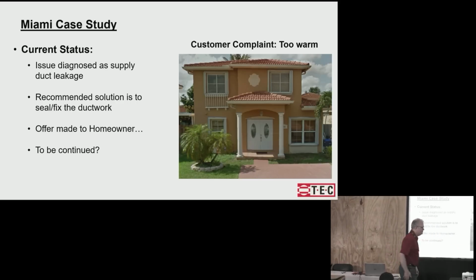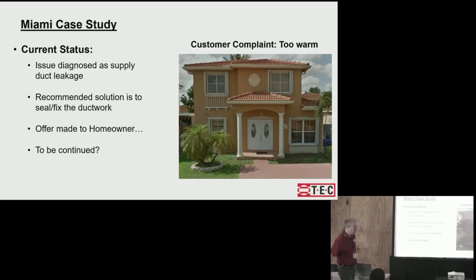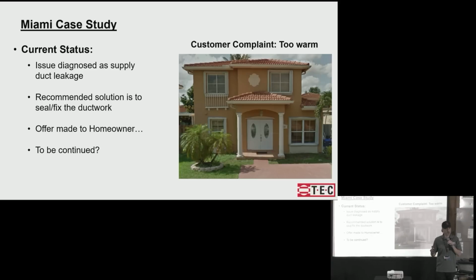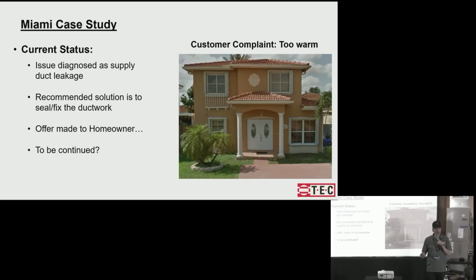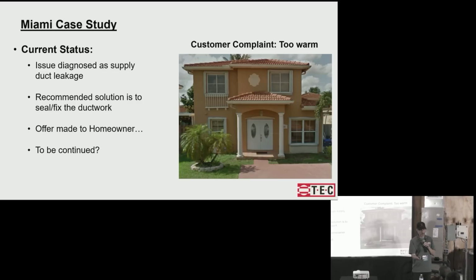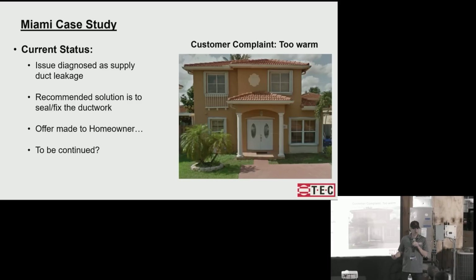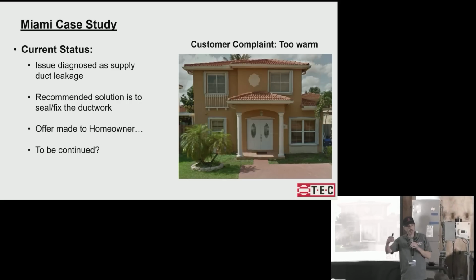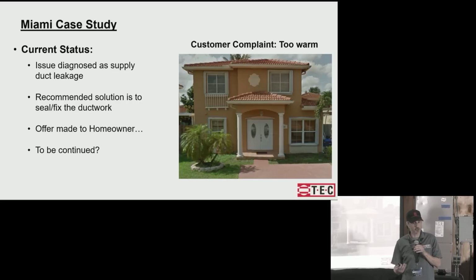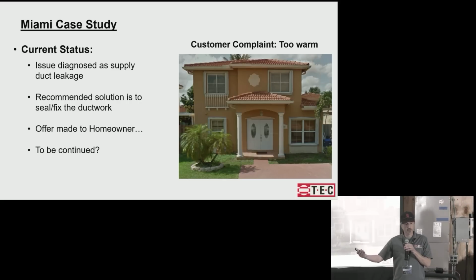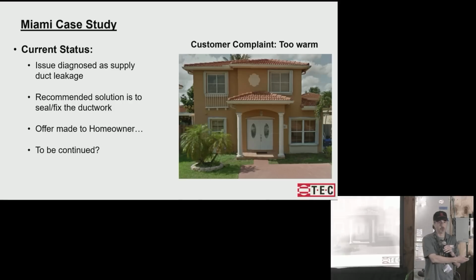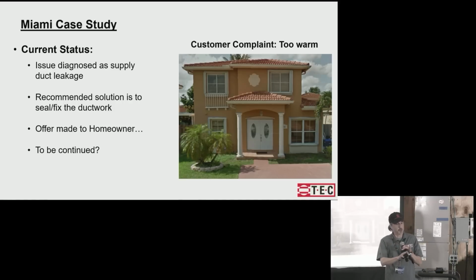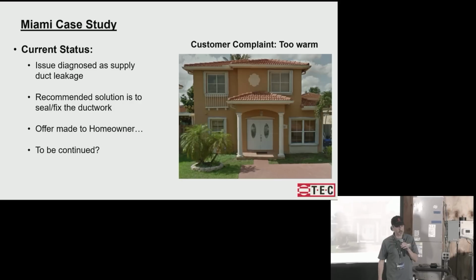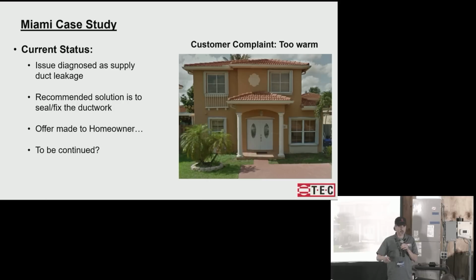I think the other thing to think about on your question might be, what are the common settings in the zones for the way they're set up? Meaning, if they're complaining about an issue, again, I don't know what condition you're dealing with, but you could do this test under a lot of different situations. And that simple test that Jenry did, the house depressurization, would tell you, when these zones are calling, this is the depressurization. When all the zones are calling, this is the depressurization. There's nothing magical about how you have to adjust the system. Try to hit the common settings, the way they're actually operating, that are causing the homeowner to say, I hate this, this is not comfortable, please fix it.